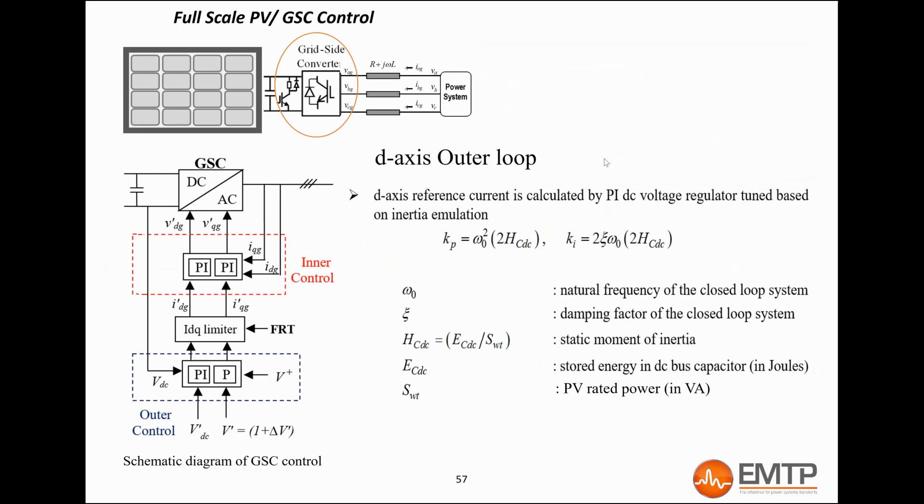On the grid side, the DQ-transformation angle follows the voltage here, right after the choke RL filter at the converter transformer terminal. The D component corresponds to the real power and the Q component corresponds to the reactive power.